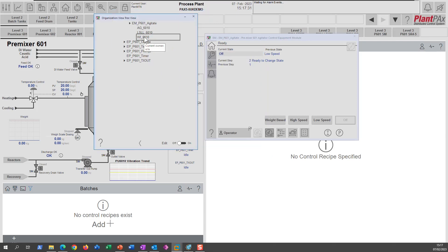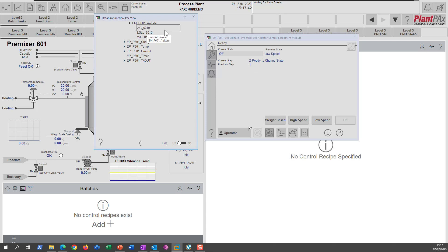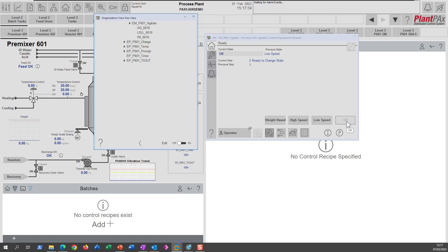We can see from the ownership tree that the agitator is now owned by this equipment module. Ownership only applies to controllable devices — monitor-only devices don't have owners. The equipment module is currently in the off state. The off button is disabled because we're already in that state. We can see what the previous state was, and we have diagnostic messages telling the user what's going on. We're in the off state and ready to change to a different state.